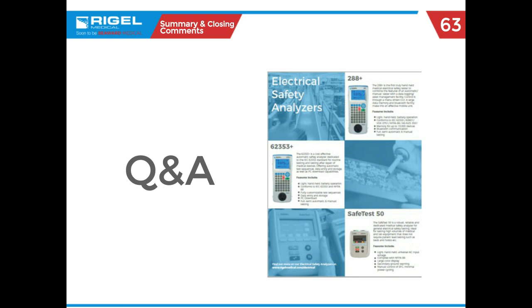Do any other governing agencies make policy on doing PMs? Yes, there are a lot of policies out there. You'll see NFPA 99 and Joint Commission. One we don't really think of is CMS — Centers for Medicare and Medicaid Services — which actually puts out policies on equipment testing for reimbursement for your hospital.